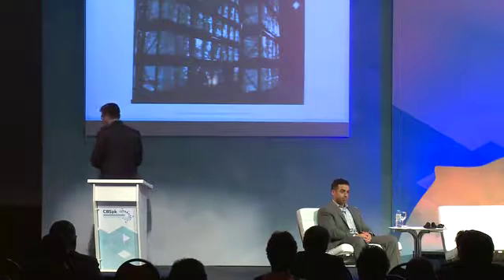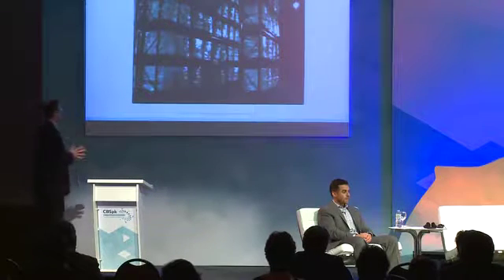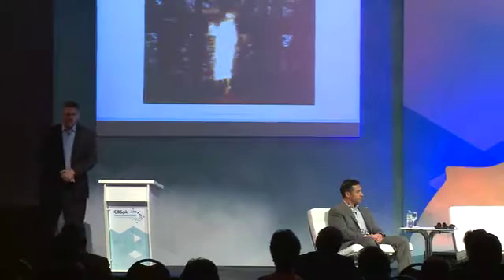So this is not the best video quality in the world here, but there's going to be plenty of fire, so you're not going to miss it. This is, again, 12-meter tall building, exposed expanded plastic, something that could not be protected in the 2013 edition NFPA 13. One level of in-rack sprinklers, only in the longitudinal flue. Fire started out on the face, 2 igniters.